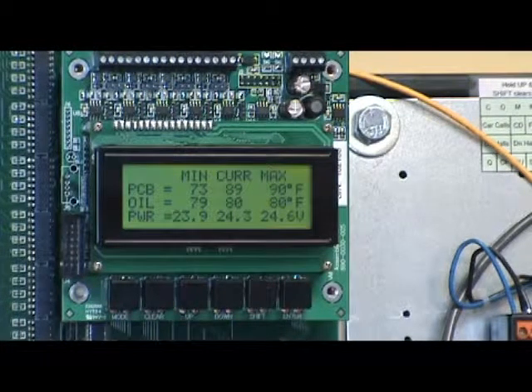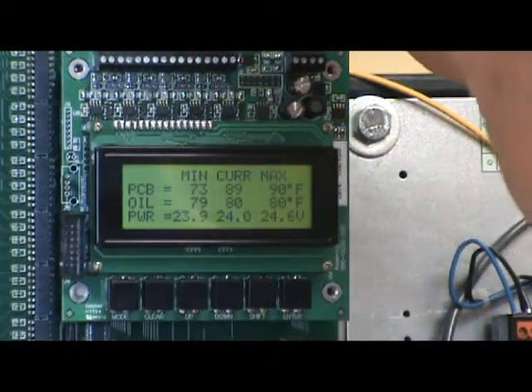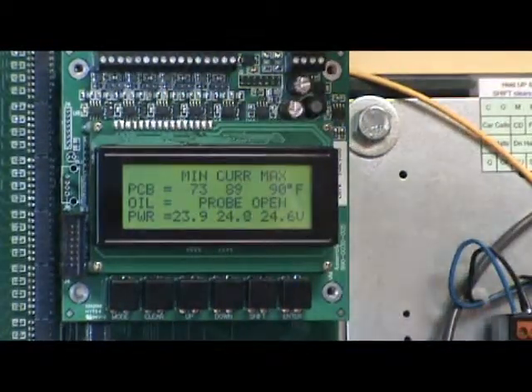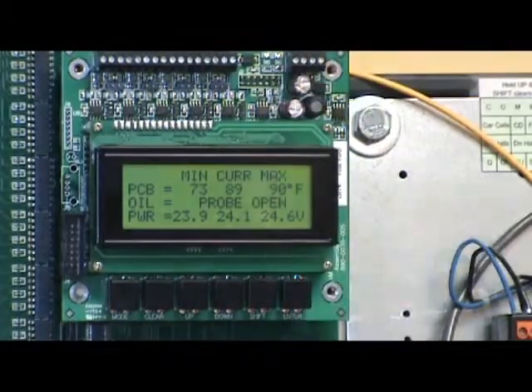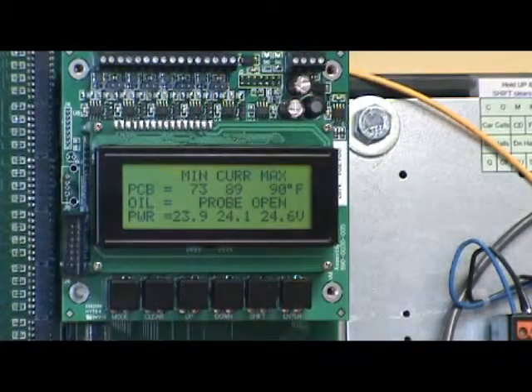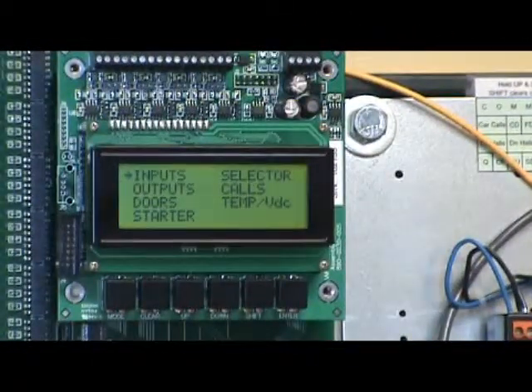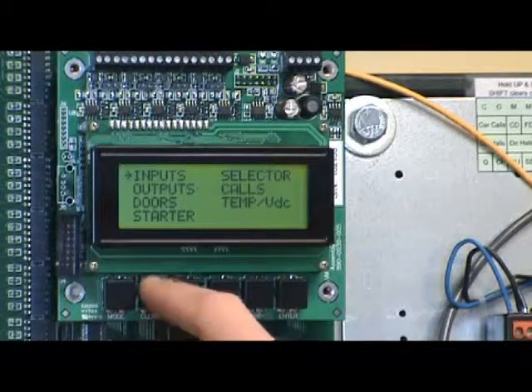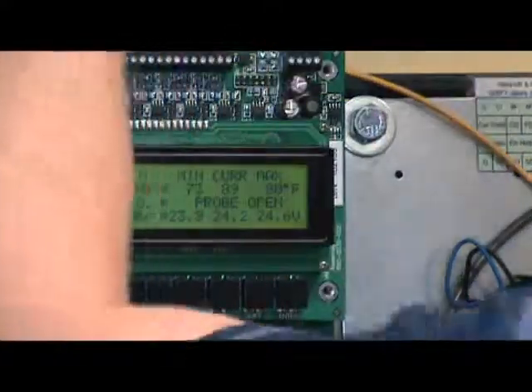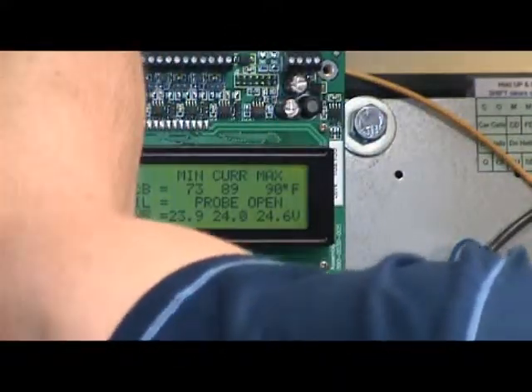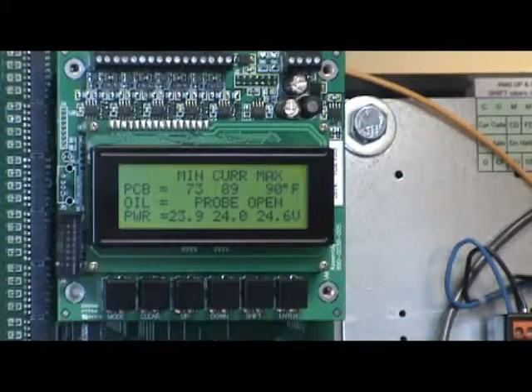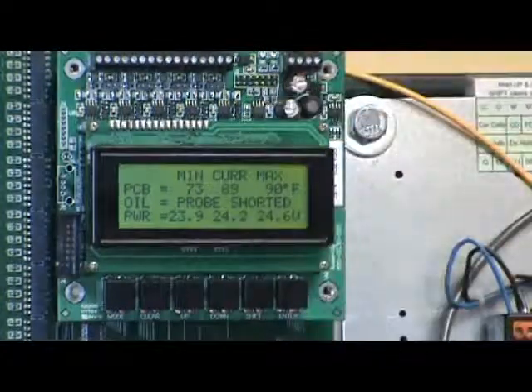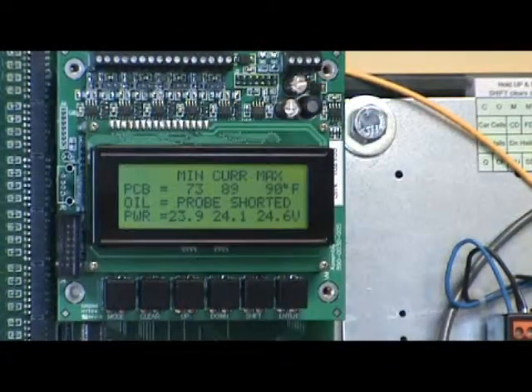If for some reason you don't have both of your wires hooked up, you're going to see a message that says probe open. That means that the probe is not hooked up. I have actually disconnected the sensor now, and I'm going to show you what happens. We're going to monitor the temperature when you short out this thing. It's not going to blow anything up, so don't panic. Just because I'm shorting out, it's going to give you a message that says probe shorted. Anytime it says probe open or probe shorted, all viscosity and hot oil features are disabled, so that we're not going into some false operation.